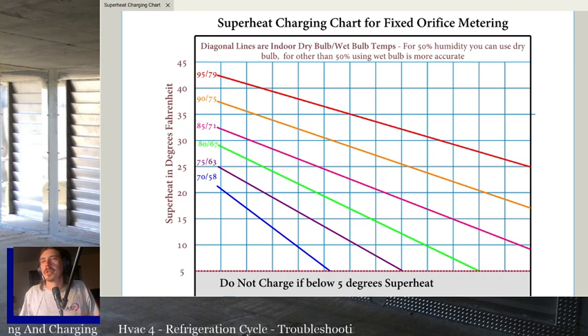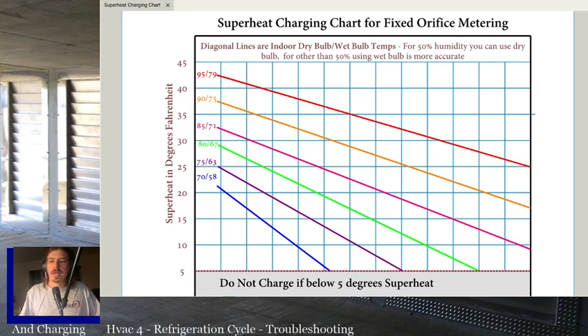This is superheat charging chart for fixed orifice metering. You'll see a few different ones. I might make a table too, or you can download tables online where they'll give you like indoor temperature, outdoor temperature, and you can just kind of line up the columns and rows that way and see where your superheat should be if you're dealing with the fixed orifice. I always kind of like Trane's one, so this is my rendition of Trane's superheat charging chart.